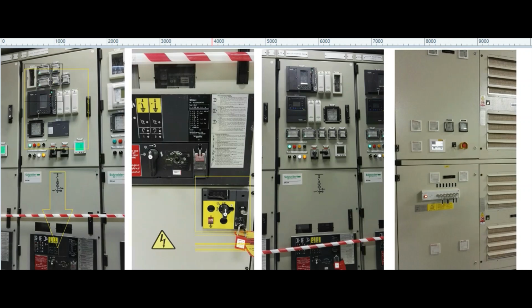So this is the lockout tagout system, where the circuit breaker is in test position and earth switch is connected with ground. So you cannot switch on the circuit breaker unless you open this padlock and switch off this earth switch. So there is the interlock. Before putting the circuit breaker in service position, you need to remove this padlock and place this earth switch in off position.